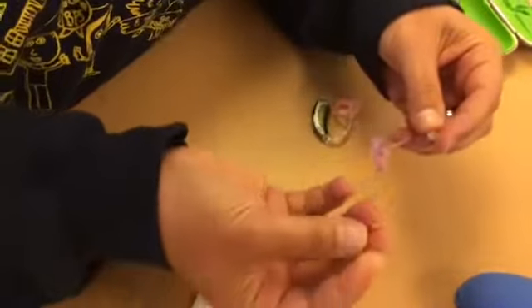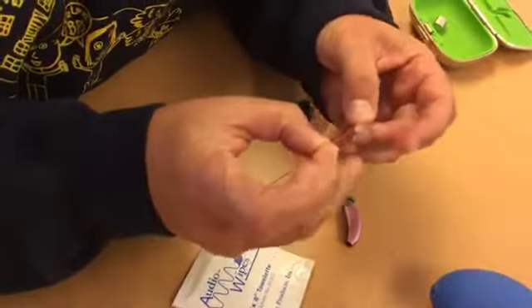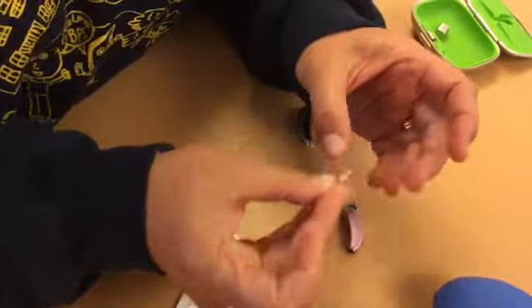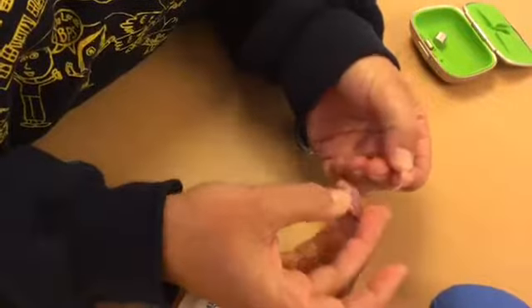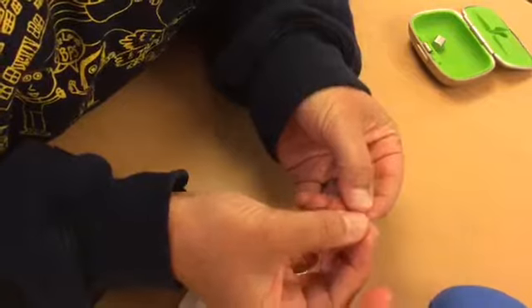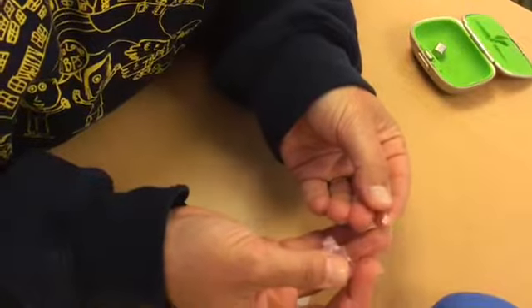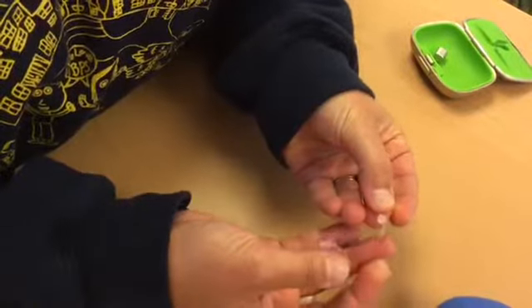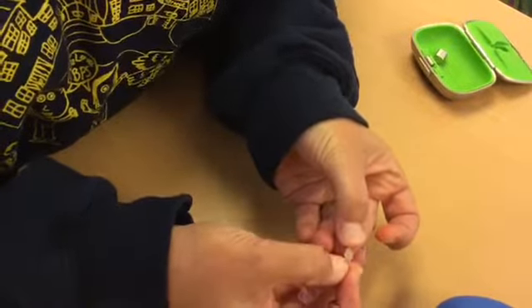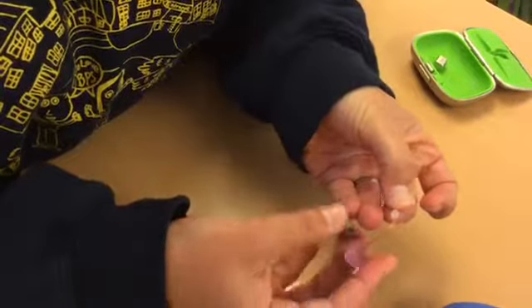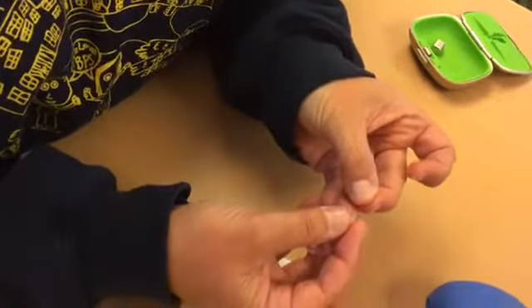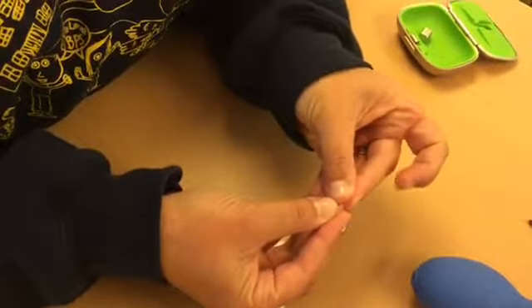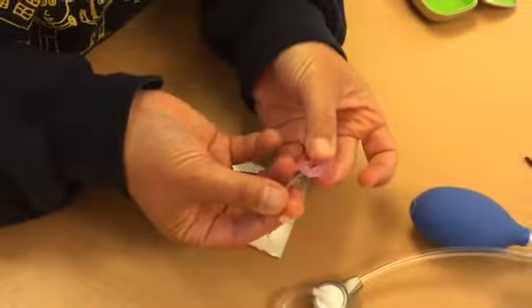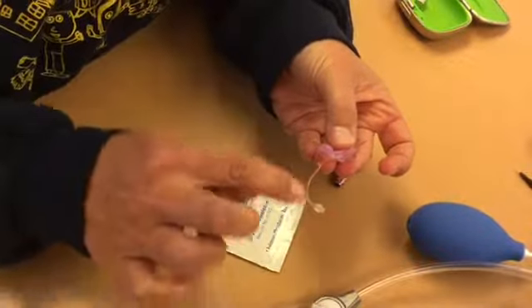But what you can do is you could take the tube off by twisting the device. Whoop, you won't break it. And using this really thin red sort of floss, I can floss this through this skinny tube and actually make sure that there is nothing that's blocking the air. And also what happens with the skinny tube is it can get pinched off and it actually stops the air from going so that the device won't work. So this actually threads all the way through, and that tells me that there is nothing blocking the tube.